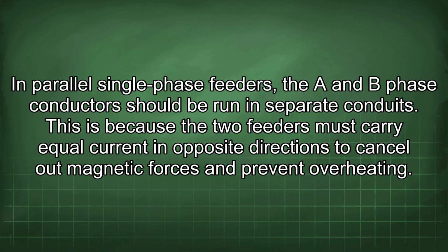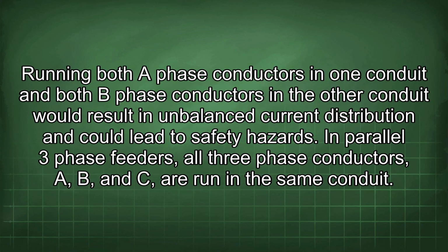In parallel single-phase feeders, the A and B phase conductors should be run in separate conduits. This is because the two feeders must carry equal current in opposite directions to cancel out magnetic forces and prevent overheating. Running both A-phase conductors in one conduit and both B-phase conductors in the other conduit would result in unbalanced current distribution and could lead to safety hazards.